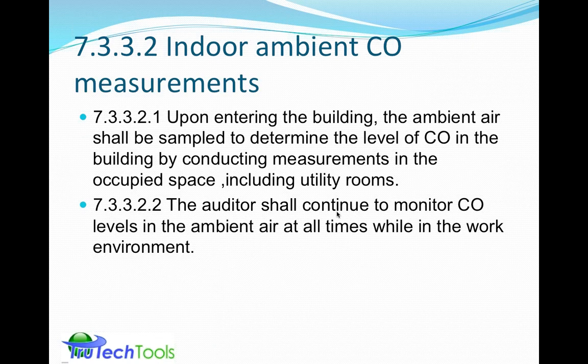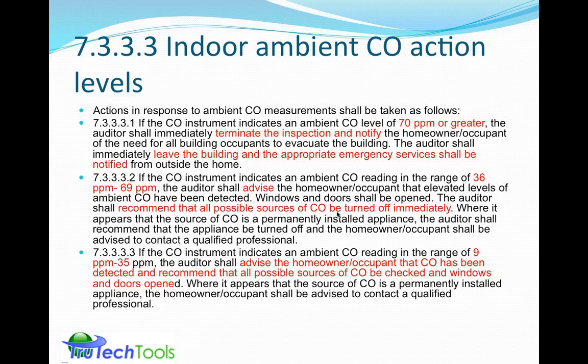So when you enter the building, you measure the CO in the occupied space, including utility rooms, and continue to monitor when you're in the work environment. That's why it's so important to have a constant duty, always on CO monitor. Now this gets a little bit dense here. I tried to highlight the salient points. I'll try to work on this slide a little bit better for next time.